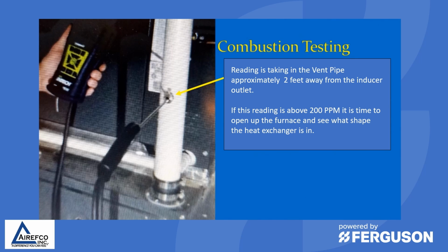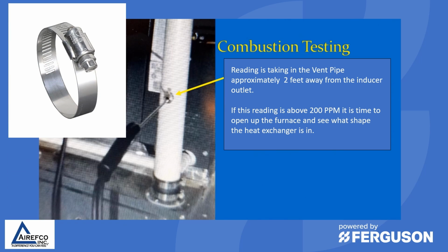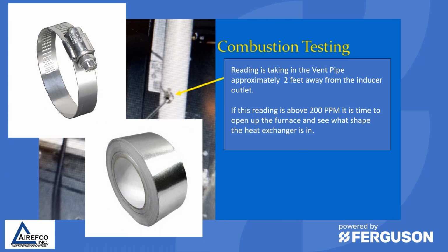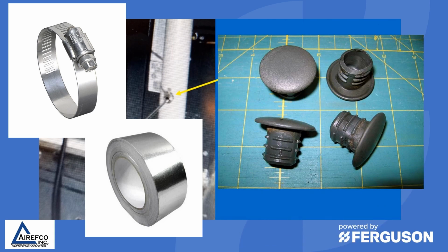Once you have completed the test, there's a couple of ways that you can seal this hole that you had to drill for your combustion meter testing. You can use a hose clamp and silver tape by putting the silver tape across the hole and then using the pipe clamp to seal it and hold it in place. Or there's also pipe plugs that are available to put in holes that you drill in PVC.